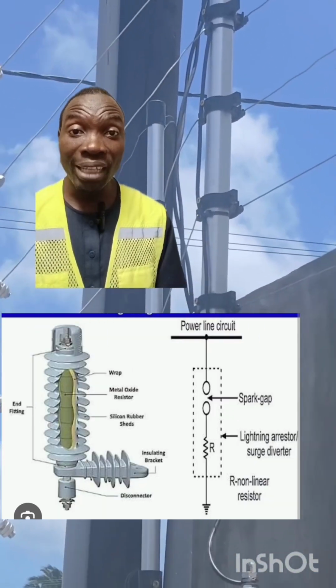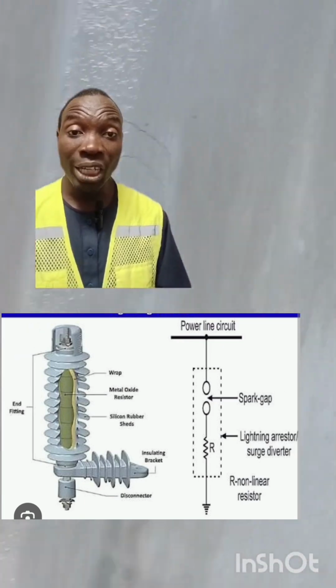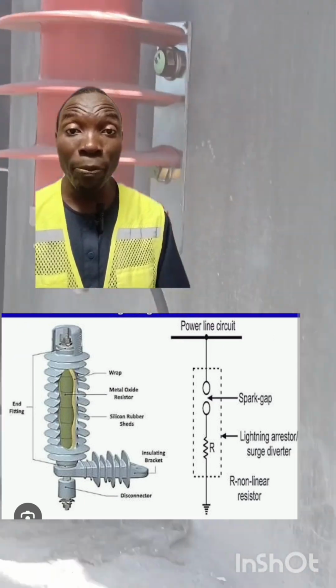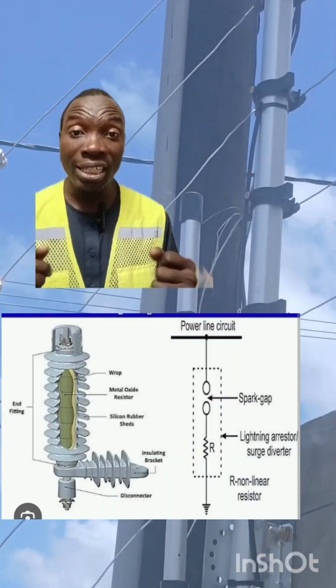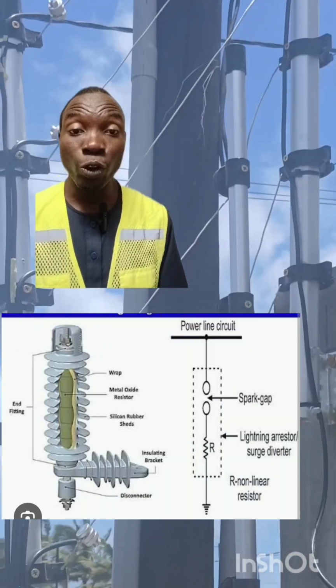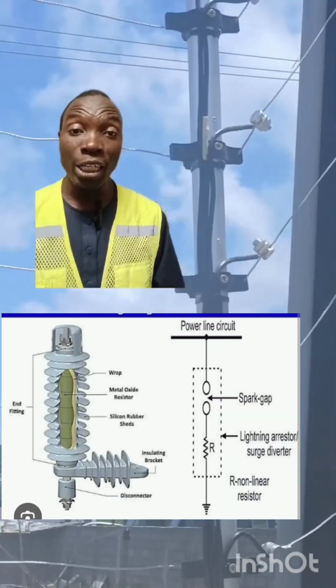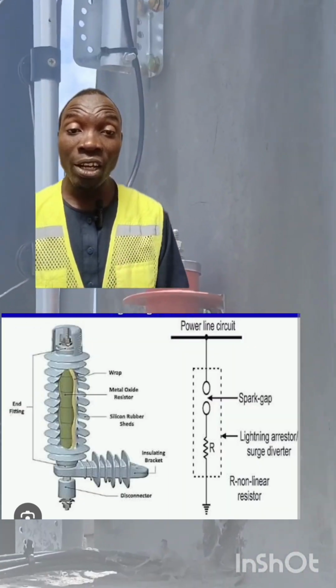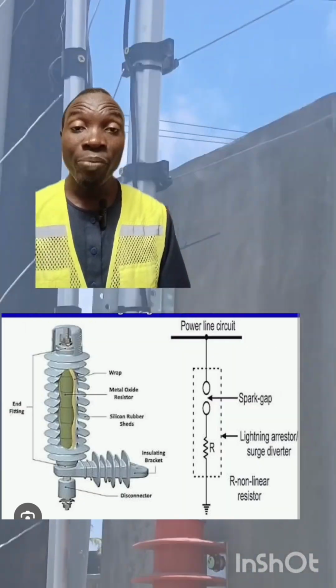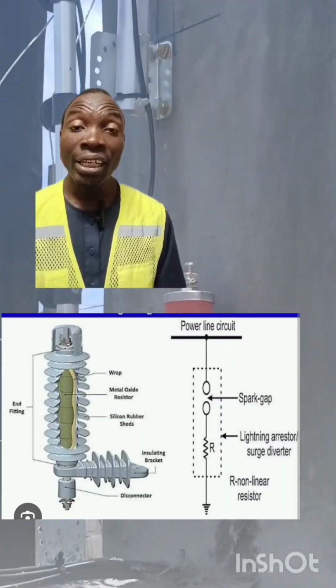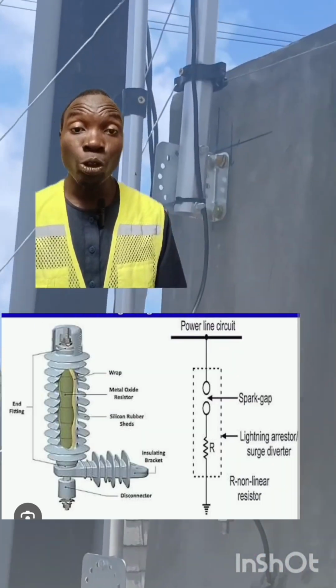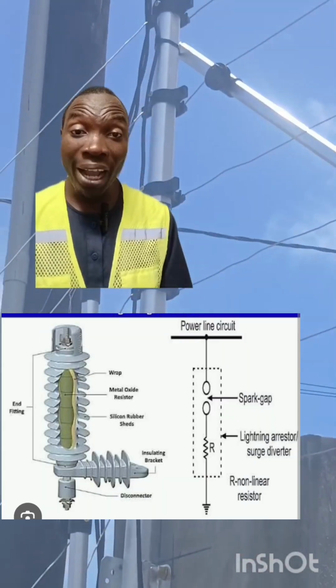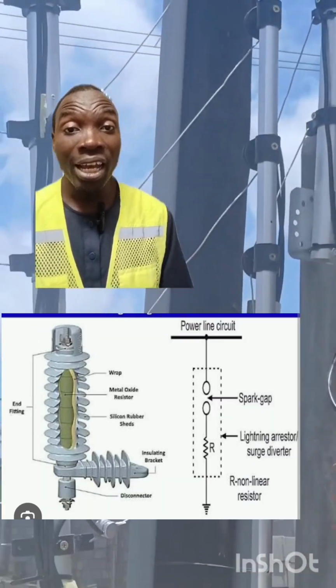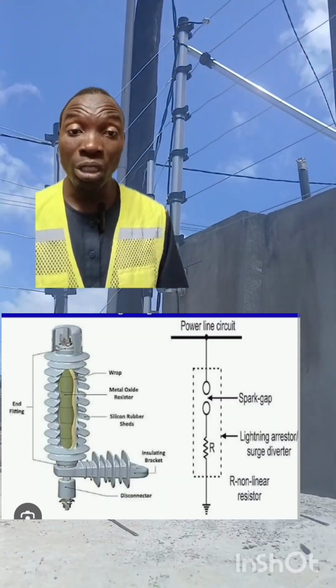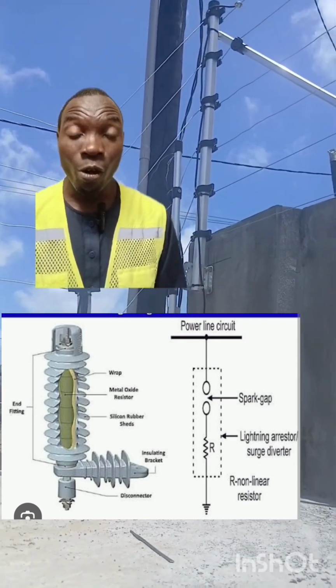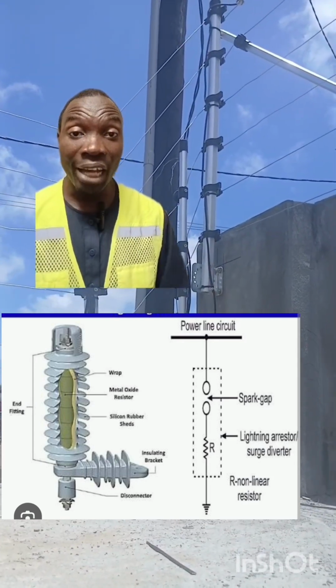But whenever it rains and there's lightning, the voltage accompanying it is usually at a higher potential - high enough to make the voltage jump the gap between the upper and lower terminal. The lower terminal of the thunder arrestor is grounded, so whenever there's lightning, the voltage jumps the spark gap between the upper and lower terminal, then flows down through the earth continuity conductor to the ground, where it is grounded.